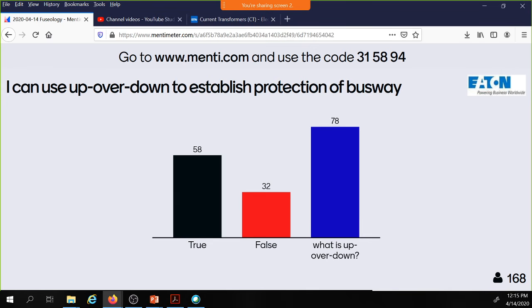And yes, you can use the current let-through tables and curves from the current limiting devices to show that you can protect busway, because it's a static device. I can't necessarily do that with a dynamic device like a circuit breaker, but I can do it on static type devices like busway, cables, and other similar things that aren't trying to open the circuit at the same time that the fuse is trying to open the circuit. So the right answer here is true, those 58. And we're going to talk about this in a little bit more detail, and I'll give you some good reference information to put into your library, either your electronic library or your physical library.